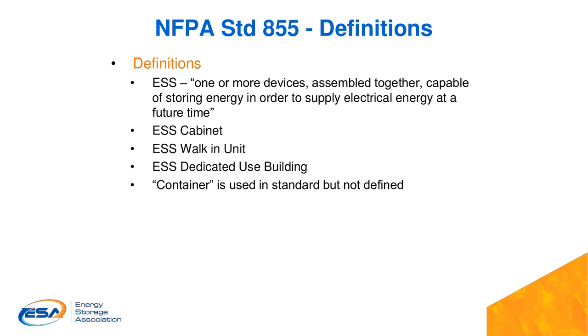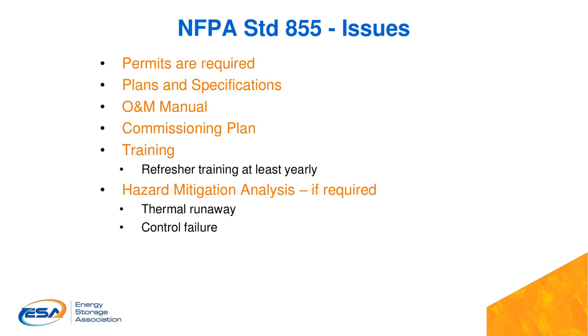There are also definitions for cabinets, walk-in units, dedicated use building. The word container is used in the standard, but it's not defined. Just out of curiosity, NFPA 855 requires permits, plans and specifications, operator O&M manuals, a commissioning plan, training, and we're going to hear more about some of these items from Steve later on, but hazard mitigation analysis, if required, would include thermal runaway and control failures.